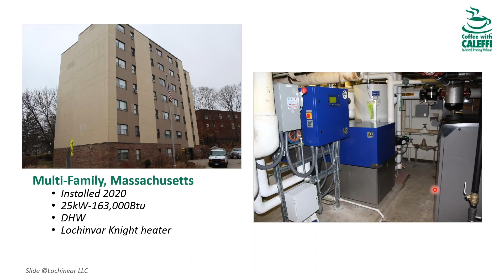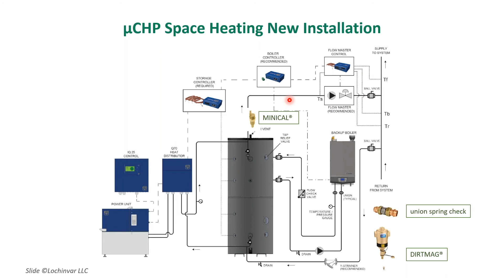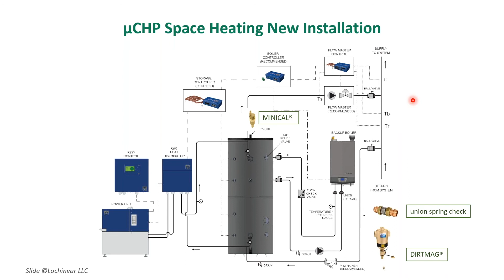Space heating, same thing. The only difference here is we have what we call a flow master controller. It communicates back to the control box, and it's monitoring the amount of heat we're getting off the cogen from the tank. It's monitoring the amount of heat that's going into the supply, and we're monitoring what's coming back through with two sensors, because we don't want to backfeed into the loop. So it will adjust both, it's got an actuator and a pump, and it'll adjust the flow rate and the pump speed to match what is needed for the system for the space heating application.